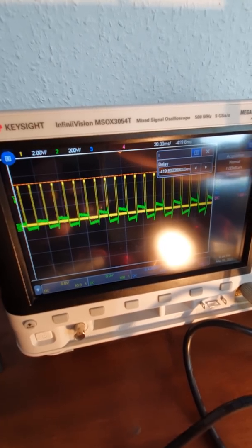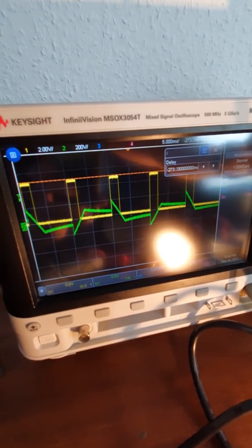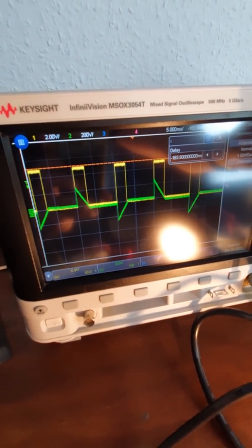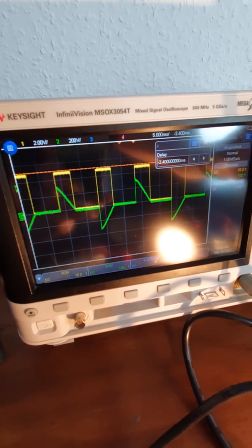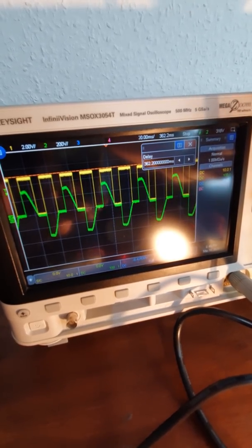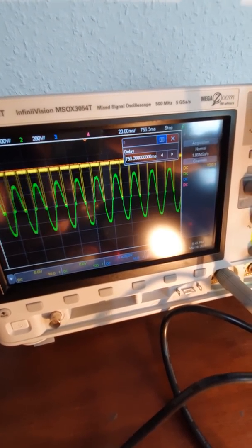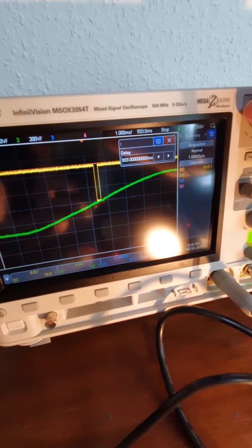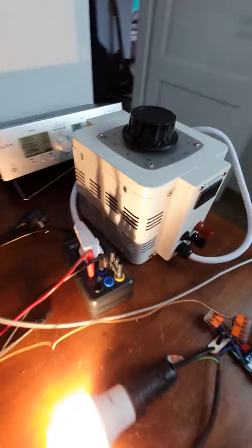The green trace is the mains voltage waveform. As time progresses, you can see the applied AC voltage increasing more and more — that's the principle: slowly increasing the phase angle to apply more AC voltage each half-cycle. This continues until we have pretty much the complete waveform applied, meaning the triac is essentially always on. That's how the soft starter works.